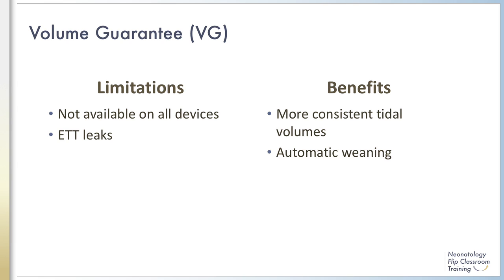Volume guarantee is not available on all ventilator devices. In addition, some devices with the volume guarantee mode do not have the capabilities of measuring the true tidal volume with large endotracheal tube leaks. These infants may require re-intubation with a larger endotracheal tube to reduce leak, or conversion to a pressure control mode of ventilation. However, some devices are able to compensate for large ET tube leaks of up to 75–80%.